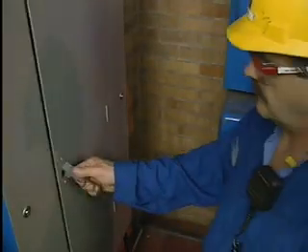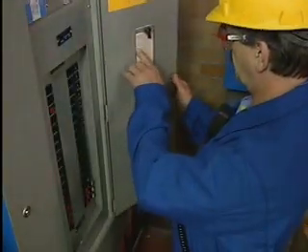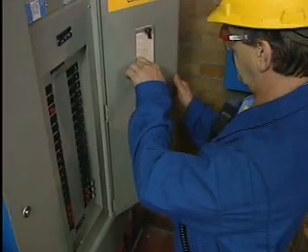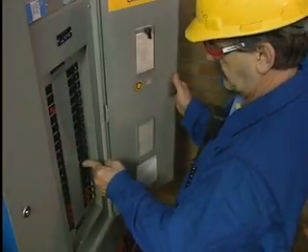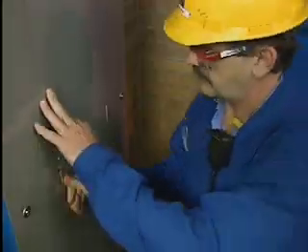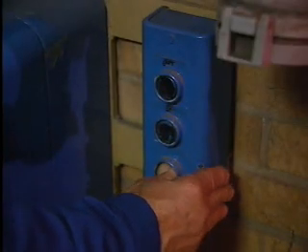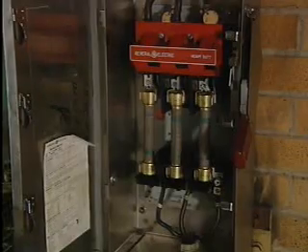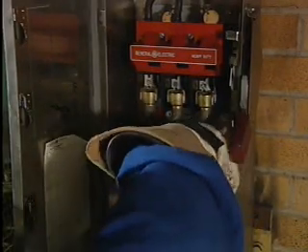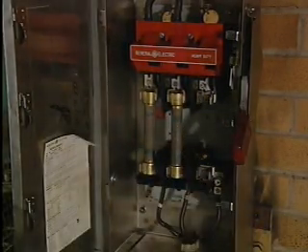To prevent an arc from forming when a fuse is pulled, the current flow through the fuse should be stopped first. This can be done by turning off the power to the fuse or by turning off the equipment that's connected to the fuse. If there's no current flowing, an arc cannot form.